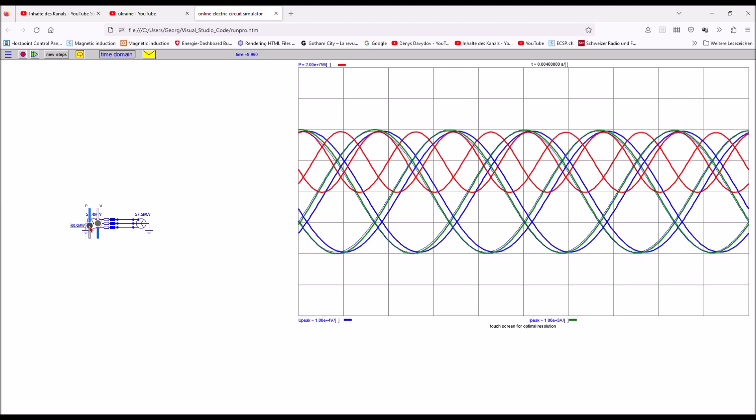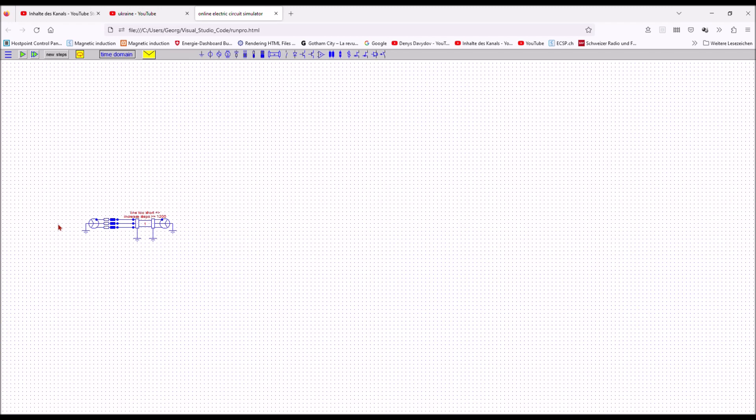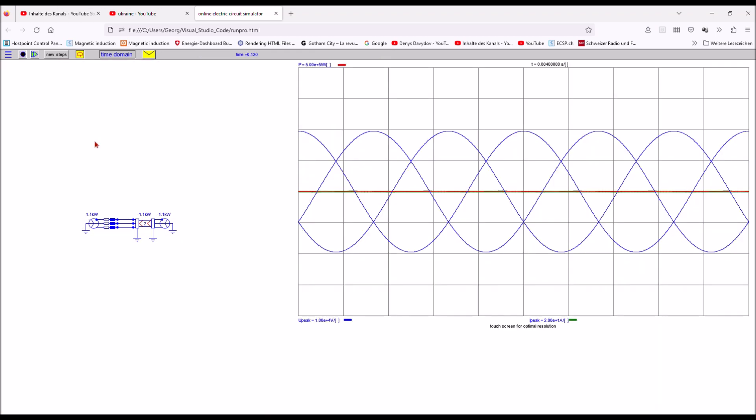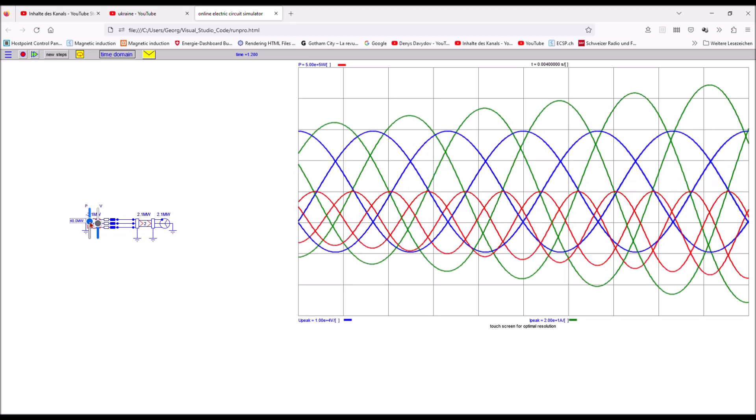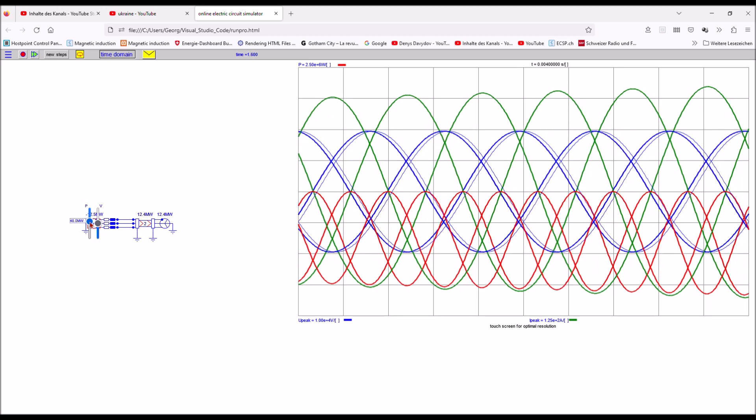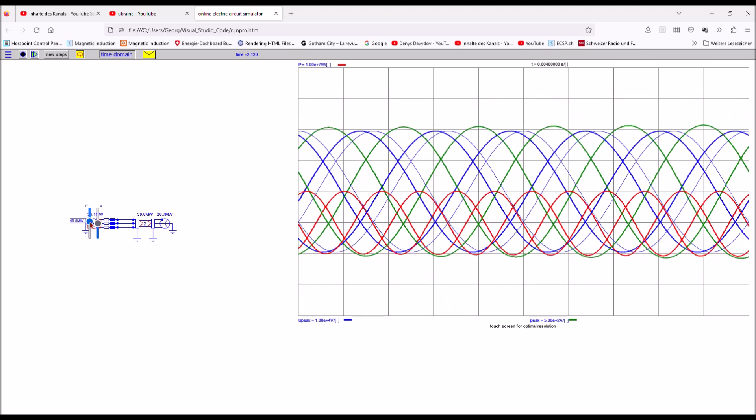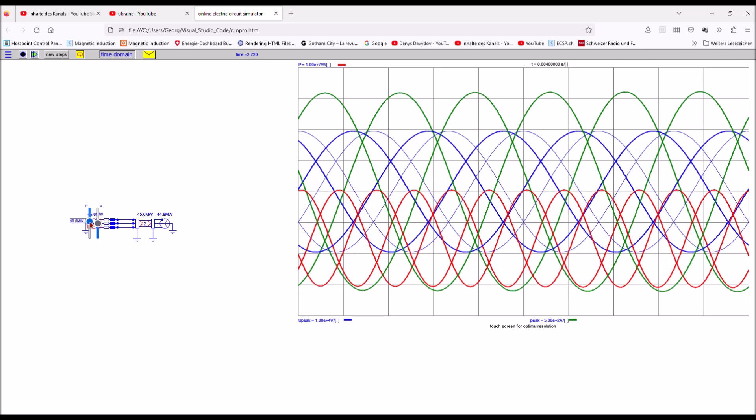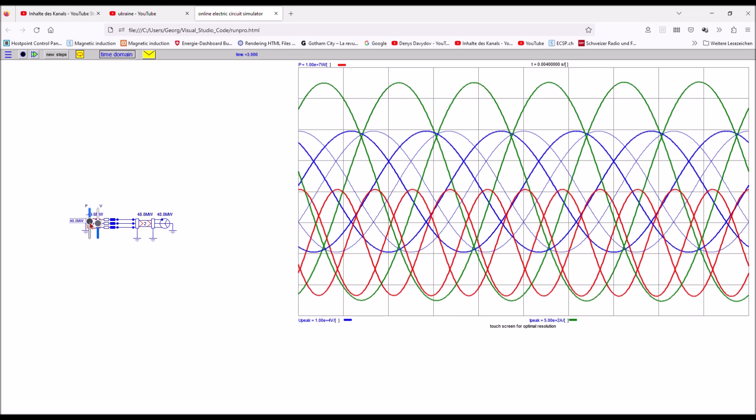We have now all the ingredients to manage our first very small power flow model. I have now added a three phase power line between our infinite bus and our generator to the left. I get a warning that the line is too short for the number of simulation steps I had before. This number in the middle of the line should be at least two, therefore I have to increase the number of steps. Now you can see the power flow direction in this line. Now I generate power which goes from the left to the right.